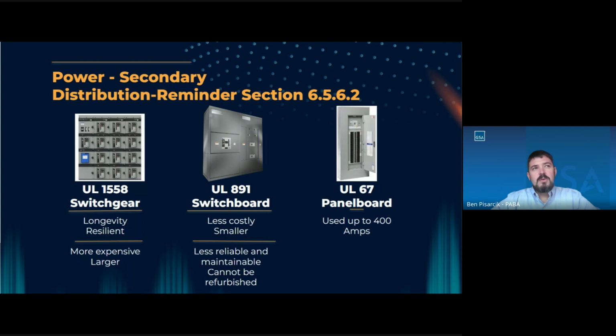So a few versions ago, we started using the UL listing to differentiate between switchgear and switchboard because so many folks, including electrical engineers, use those interchangeably, and they are two different pieces of equipment. So talking about switchgear, this is a good representative photo. These breakers, these cubicles can be racked out and removed, replaced. Typically switchgear has a longer longevity. Obviously, we know many of GSA's buildings are in our portfolio for many, many years. It's more resilient, can be refurbished, and we have a lot of those projects going on currently that are being refurbished. However, it is more expensive and it is larger, and that's the pushback we get on it sometimes.